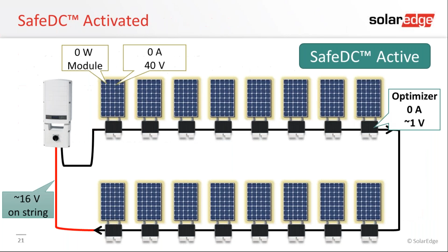Perfect. Here's the evolution of the code. We've trademarked that functionality, SafeDC, and SolarEdge has had SafeDC since 2010, well before rapid shutdown was ever a requirement. It just so happened that when the 2014 NEC and the 2015 Canadian Electrical Code, CEC, came about, we already had a solution that was integrated into our product. We just had to meet the time requirement, which was originally written as 10 seconds and then extended to 30 seconds. The 2017 code, same thing. It just defines a little bit more about how rapid shutdown has to be performed.